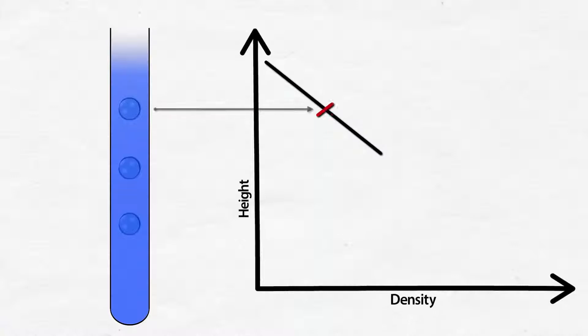The column is then calibrated by dropping in calibrated reference floats of known densities. The floats will slowly sink until each reaches liquid of its own density. This allows a relationship between height up the column and density to be determined.